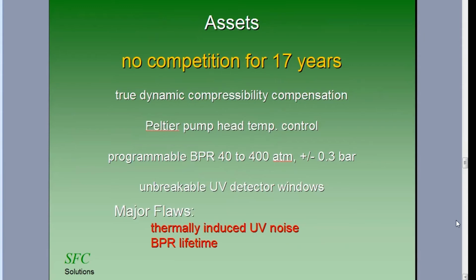Yes, there were other companies that started SFC, packed column SFC, but they all followed exactly the same thing that Dennis Deere did. They took an existing LC, clamped on heat exchangers, and used a circulating bath to cool the pump head, and got a back pressure regulator on the end. It had the same problems that Deere had originally, and that went on until the big companies jumped in later on.